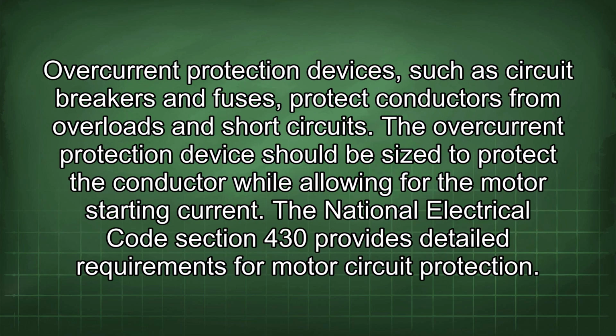Overcurrent protection devices, such as circuit breakers and fuses, protect conductors from overloads and short circuits. The overcurrent protection device should be sized to protect the conductor while allowing for the motor starting current. The National Electrical Code Section 430 provides detailed requirements for motor circuit protection.